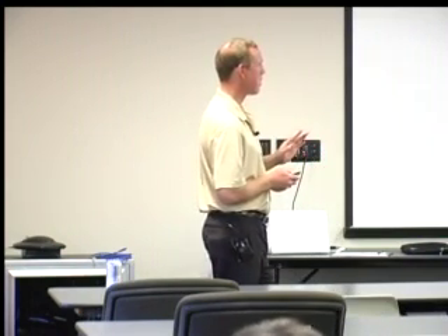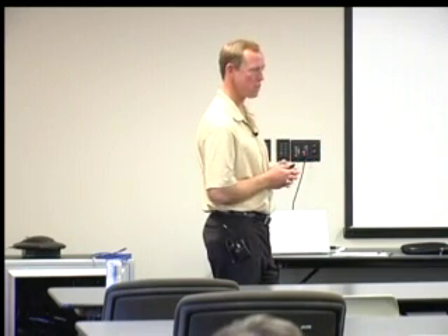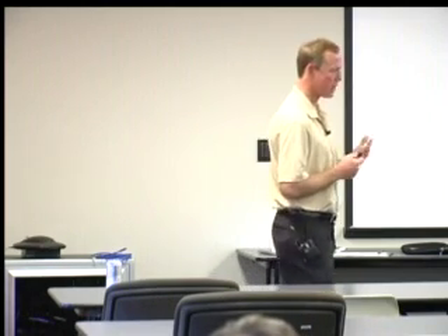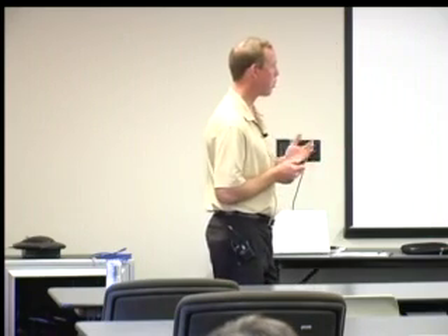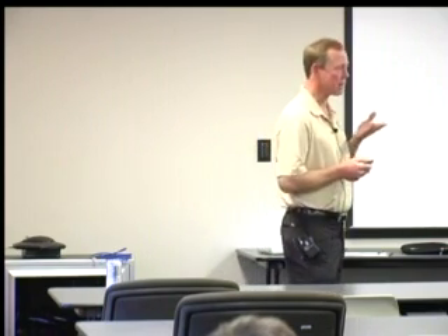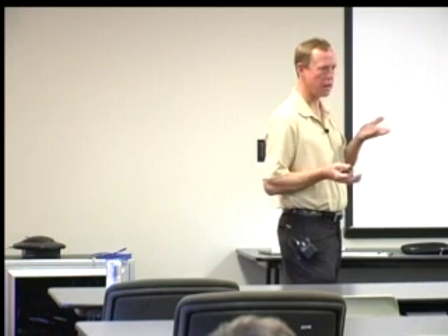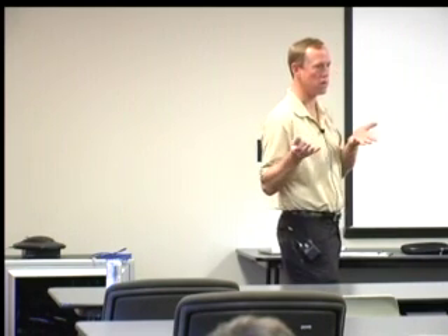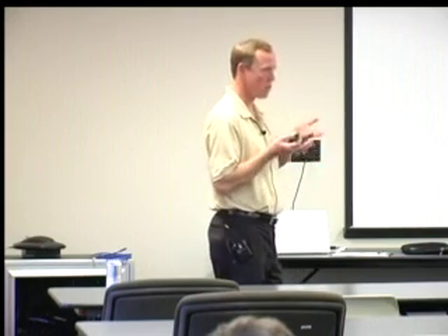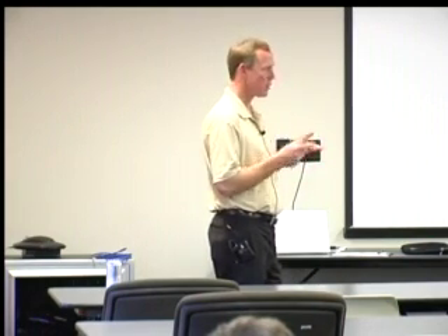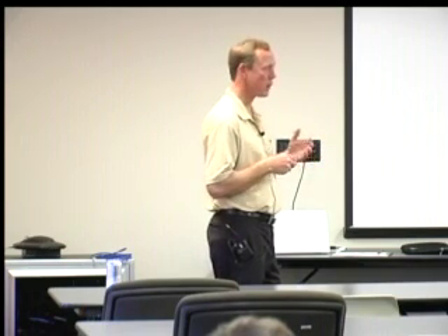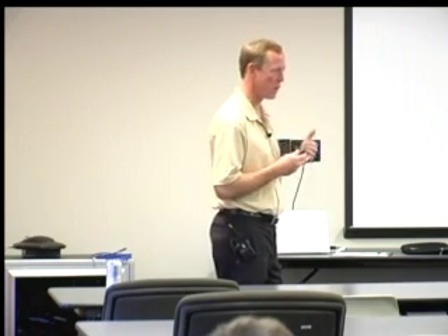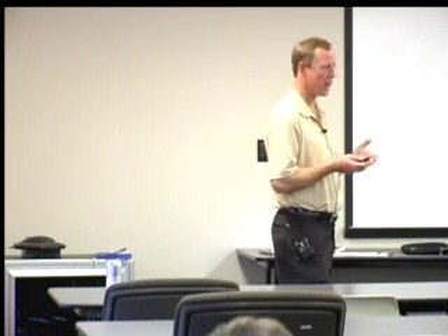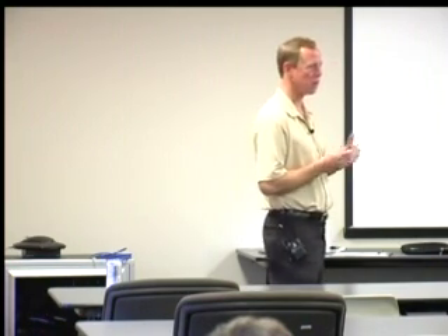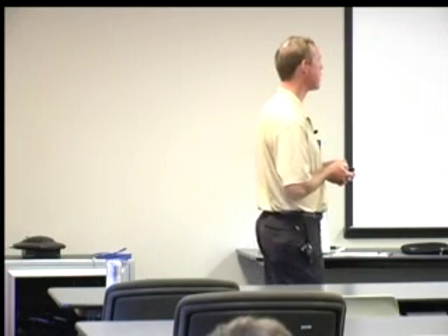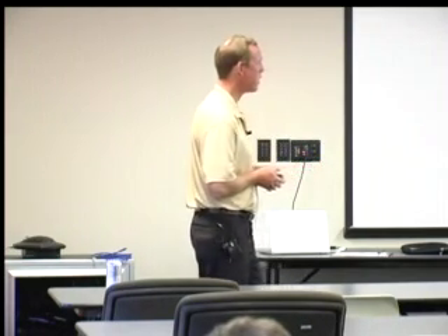Night setback is a similar thing. That's where we were able to get some gains. And I'm not a big fan of shutting down buildings in Central Florida. I'm more of a fan of the setback. I like to raise the set point when we have an unoccupied building and let it naturally warm up by itself. And what that does is that lowers the relative humidity in the space. And then the next morning we go through this optimal start procedure or whatever, and I do it in a slow method where we can draw down that moisture. You move that air real slow across the coil, and we're able to really dehumidify the space. So I'd encourage you to look at things like that.